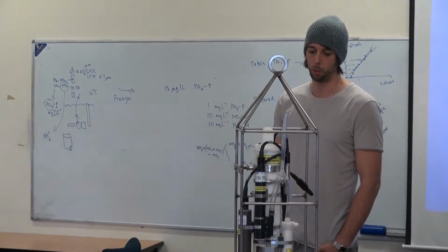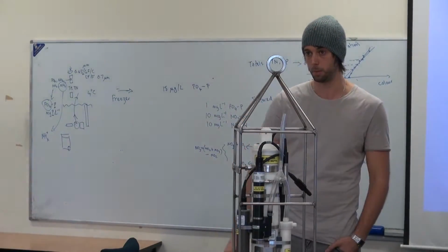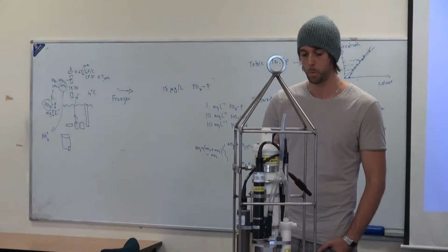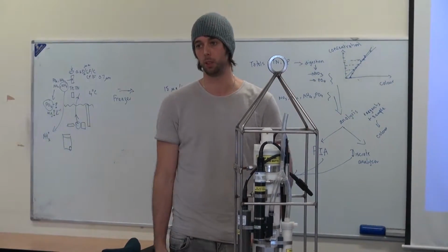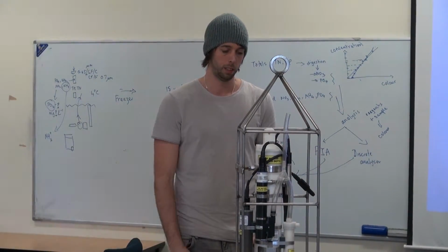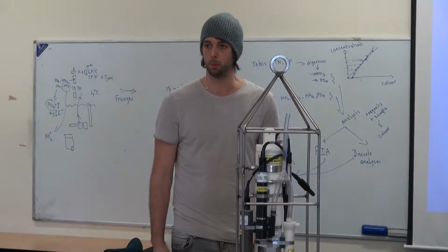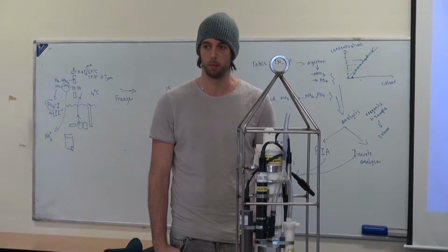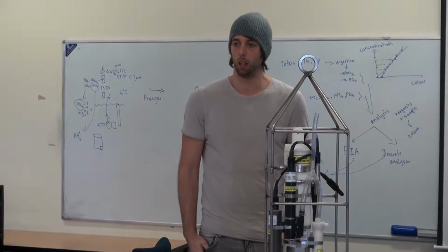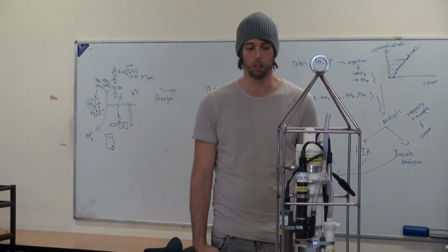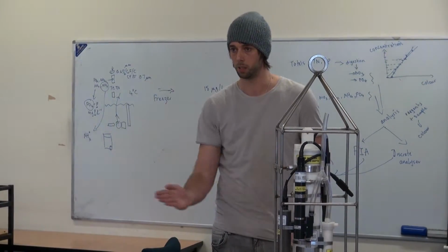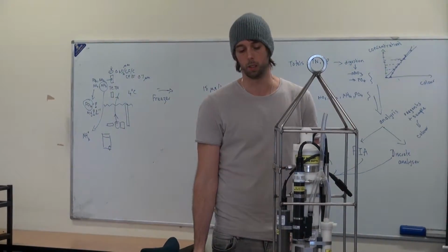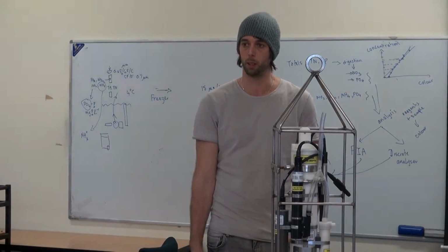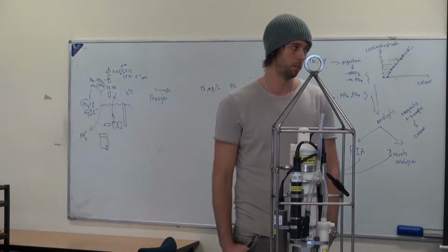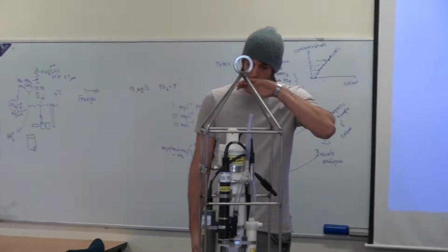So if you're interested in the whole water column, you generally want to take a few different depths of chlorophyll. And different species assemblages will fluoresce differently. It's not a one-stop shop for measurements. It's about half a dozen different depths each day you use it. It depends how accurate you're trying to be. It's very good at showing the relative concentrations through the water column. It's not so good at quantifying actual micrograms per litre chlorophyll. R squared values you get are maybe on the order of 0.7 if you're lucky.